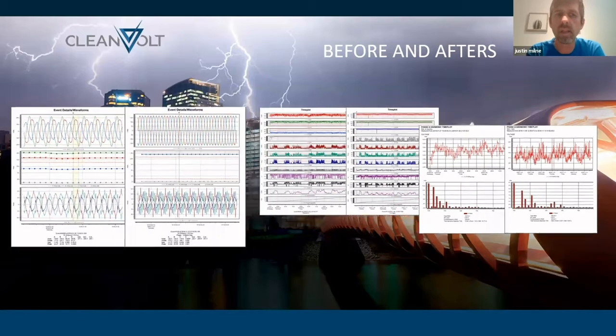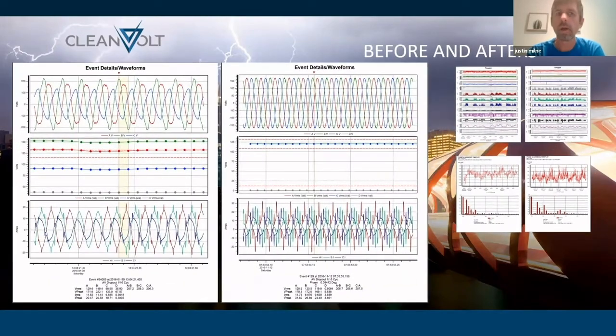As you can see in the waveform information, the waveform on the left-hand side shows the before test that we did. As you can see, this is a 120/208 system. One of the phases was stacked outside of its parameter where it should be at 120 volts. And the sine wave looked very sick. It was not symmetrical at all. As you can imagine, a piece of sensitive electronics like a circuit board is not designed to live in a world like this. And we could see clearly why they were losing a board so often.